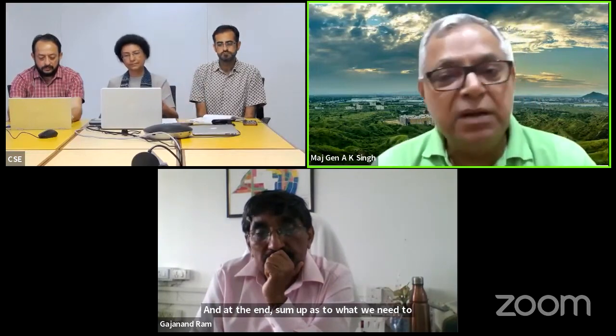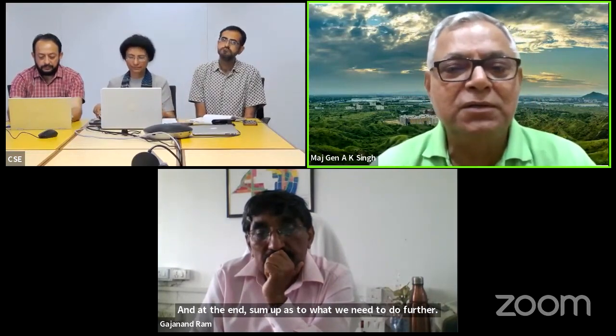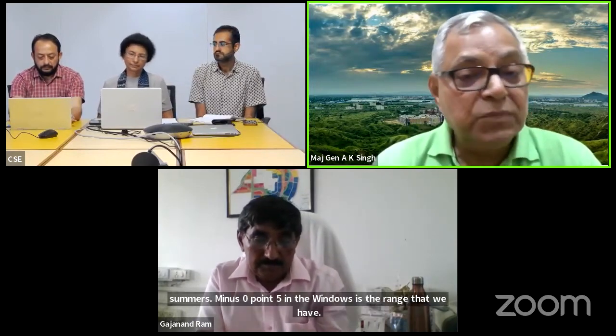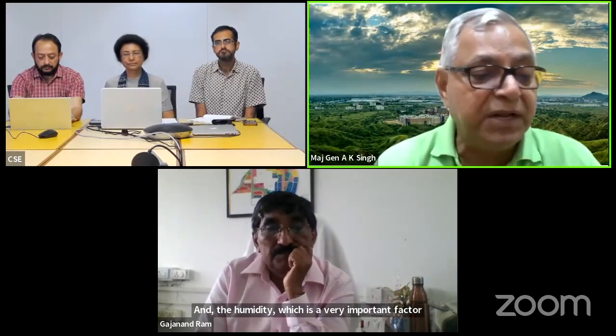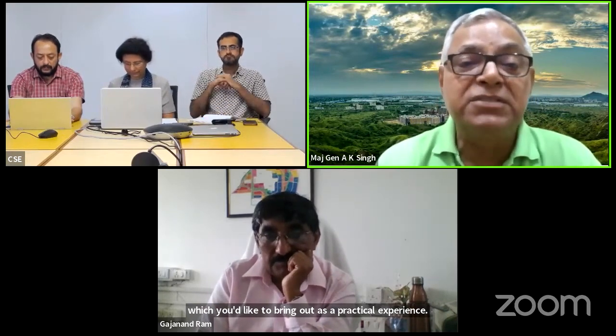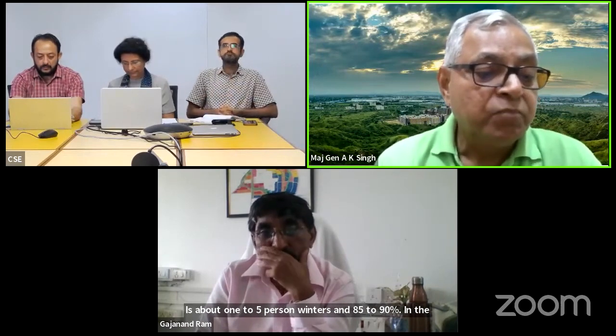Neemrana is pretty much between Nimli and Jaipur. The temperature variance is 45 degrees in summer to minus 0.5 in winter. And humidity, a very important practical factor, is about 1 to 5% in winters and 85 to 90% in the monsoons, which is the trouble creator.